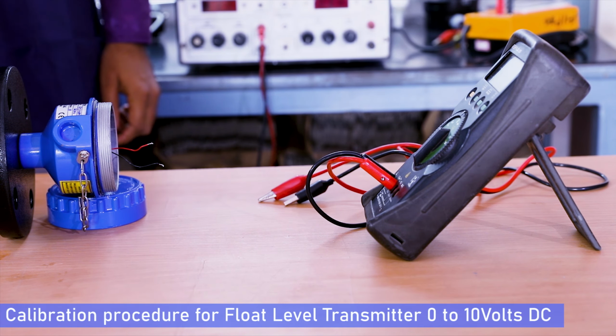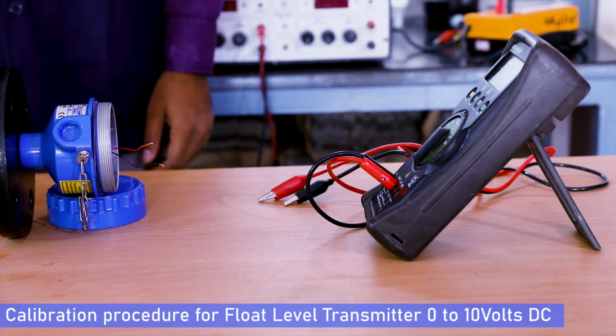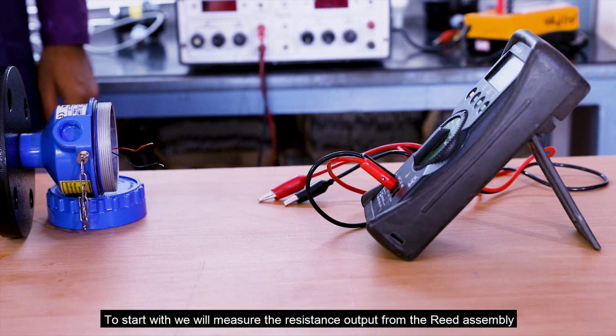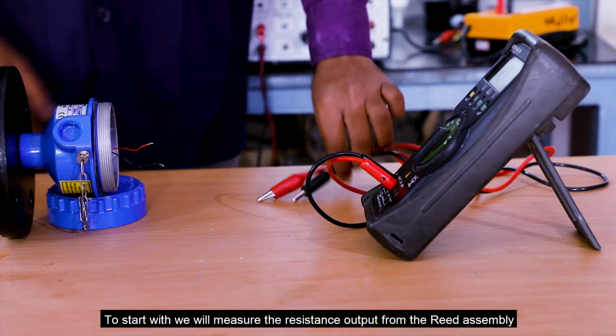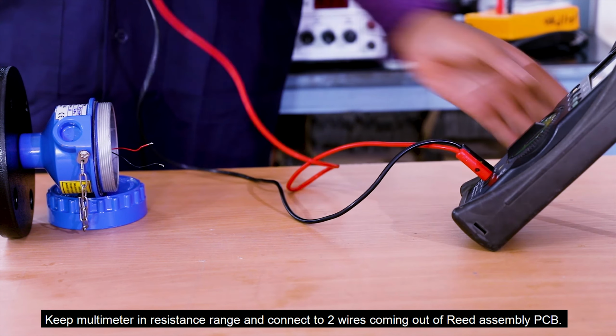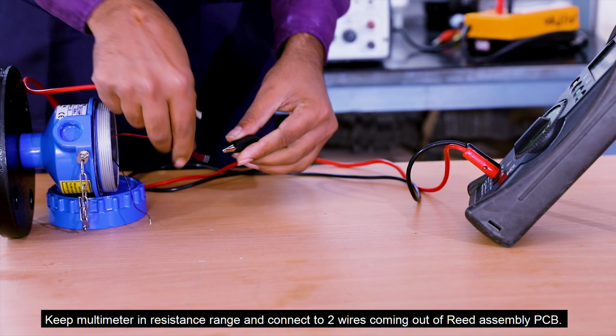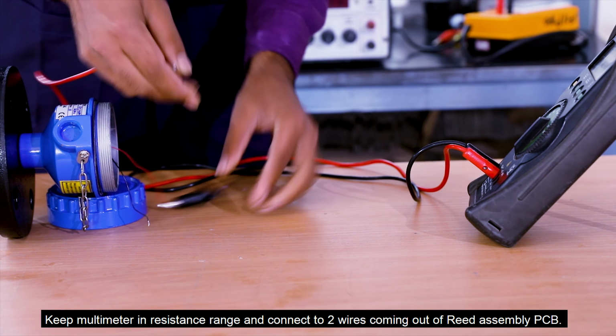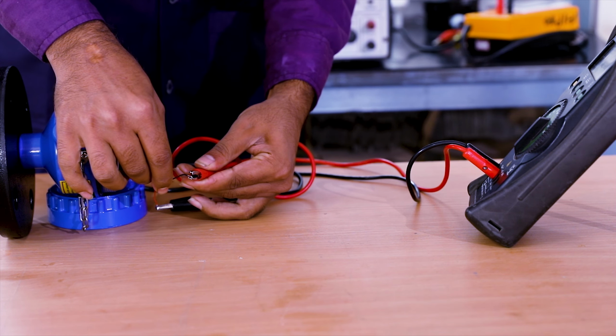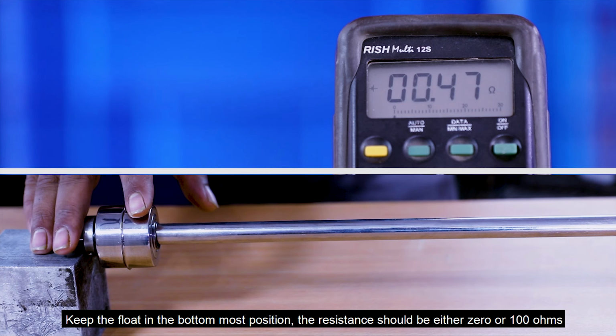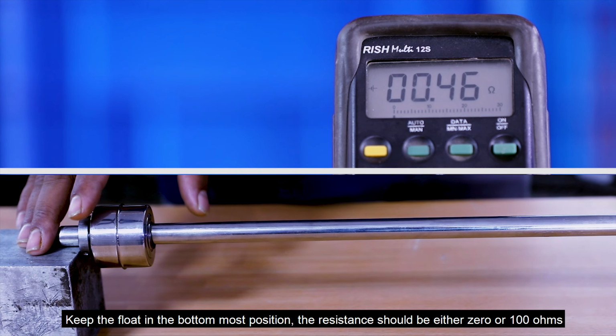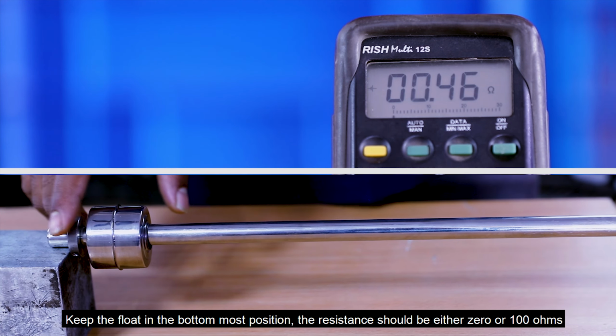Calibration procedure for float level transmitter 0 to 10 volts DC. To start with, we will measure the resistance output from the reed assembly. Keep the multimeter in resistance range and connect to the two wires coming out of the reed assembly. Keep the float in the bottommost position. The resistance should be either 0 or 100 ohms.